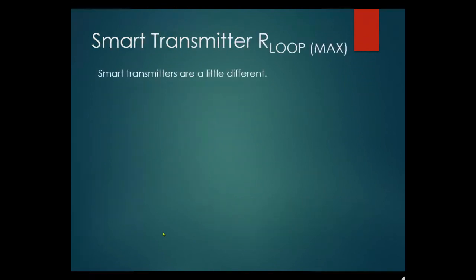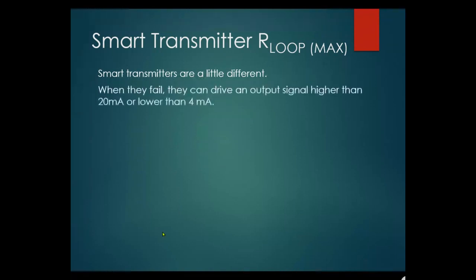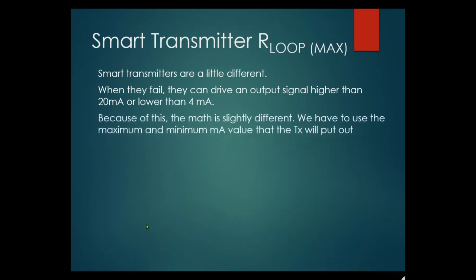Smart transmitter note: when smart transmitters fail, they can drive the output signal higher than 20mA or lower than 4mA. Depending on whether they fail toward the upper or lower range value, they signal that something is wrong with the loop — this only applies to smart transmitters. An analog transmitter wouldn't detect or signal the failure, but smart transmitters can send a fault signal to the control board.